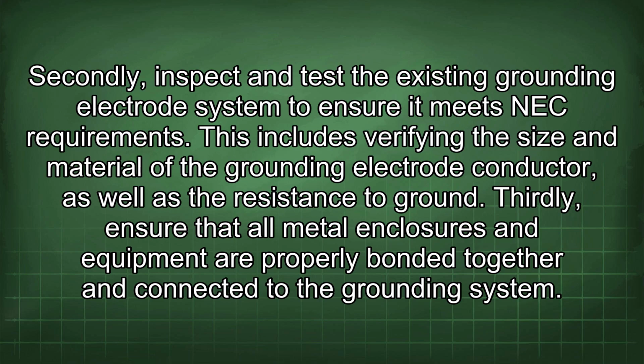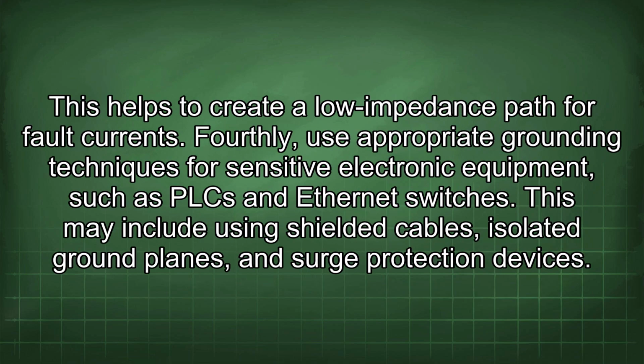Thirdly, ensure that all metal enclosures and equipment are properly bonded together and connected to the grounding system. This helps to create a low impedance path for fault currents. Fourthly, use appropriate grounding techniques for sensitive electronic equipment, such as PLC and Ethernet switches.